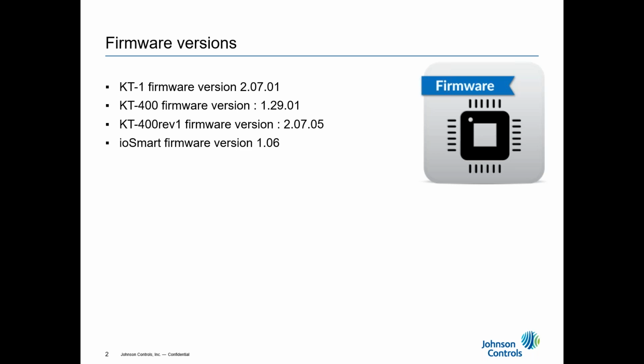Remember to upgrade your IP sites first, your IP controller, which is the master controller, and then you can go down to your secondary controllers over RS485. Always remember to upgrade one RS485 controller per loop. If you have 10 connections or 10 loops, you can do 10 controllers, just one per connection. All right?